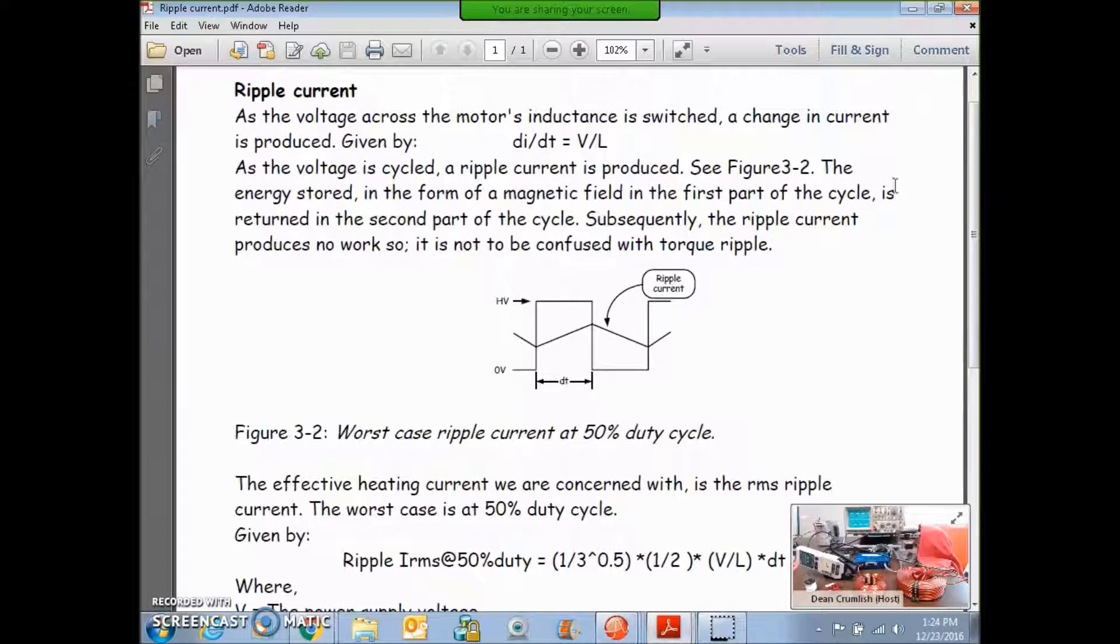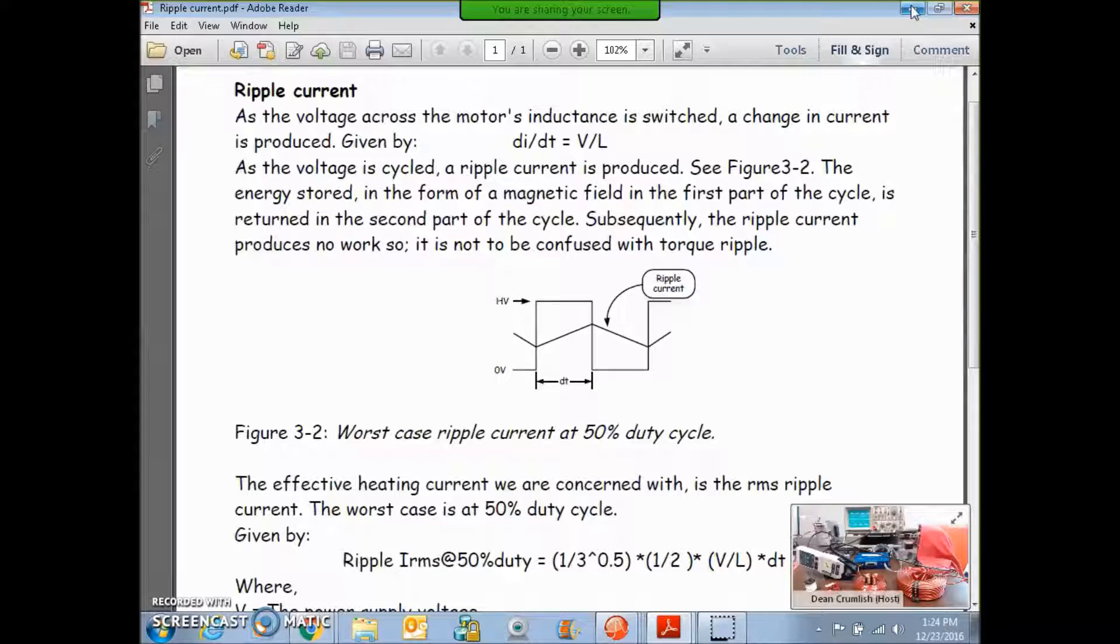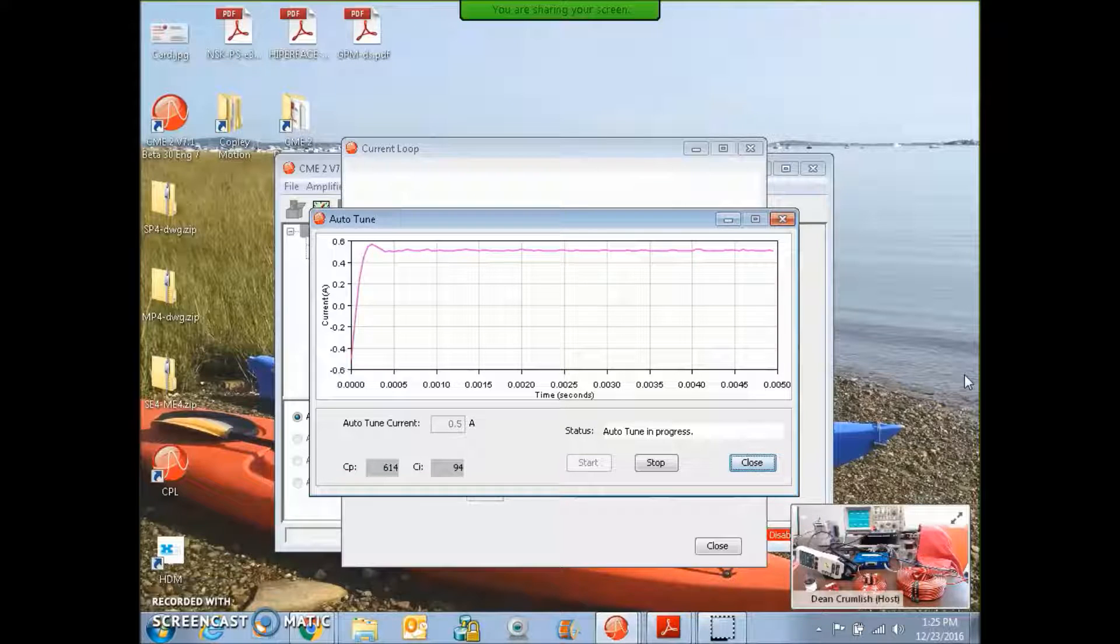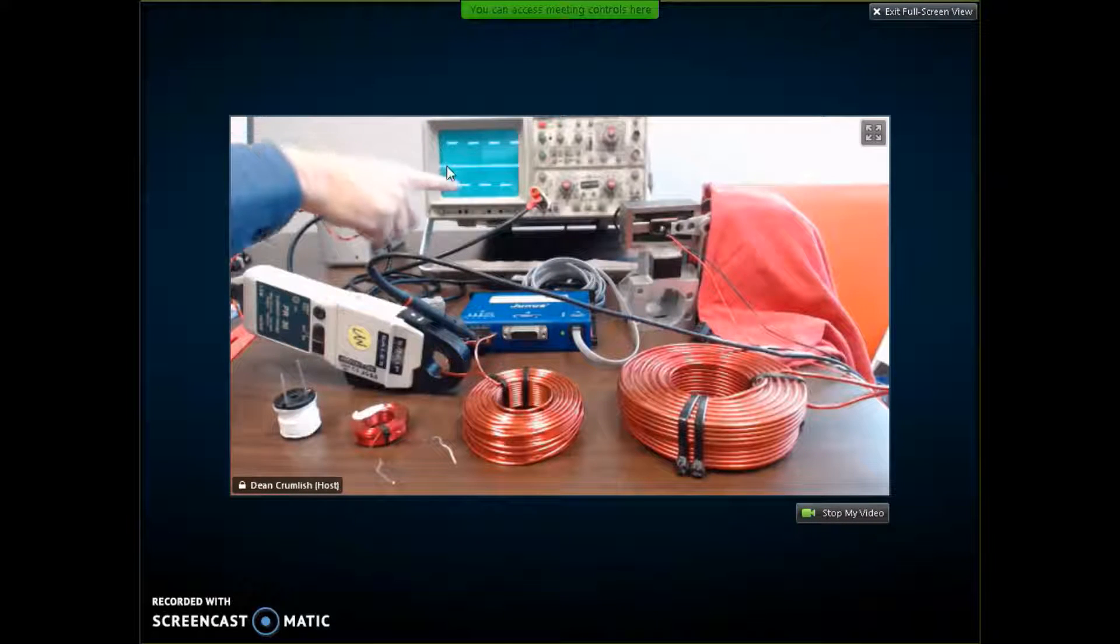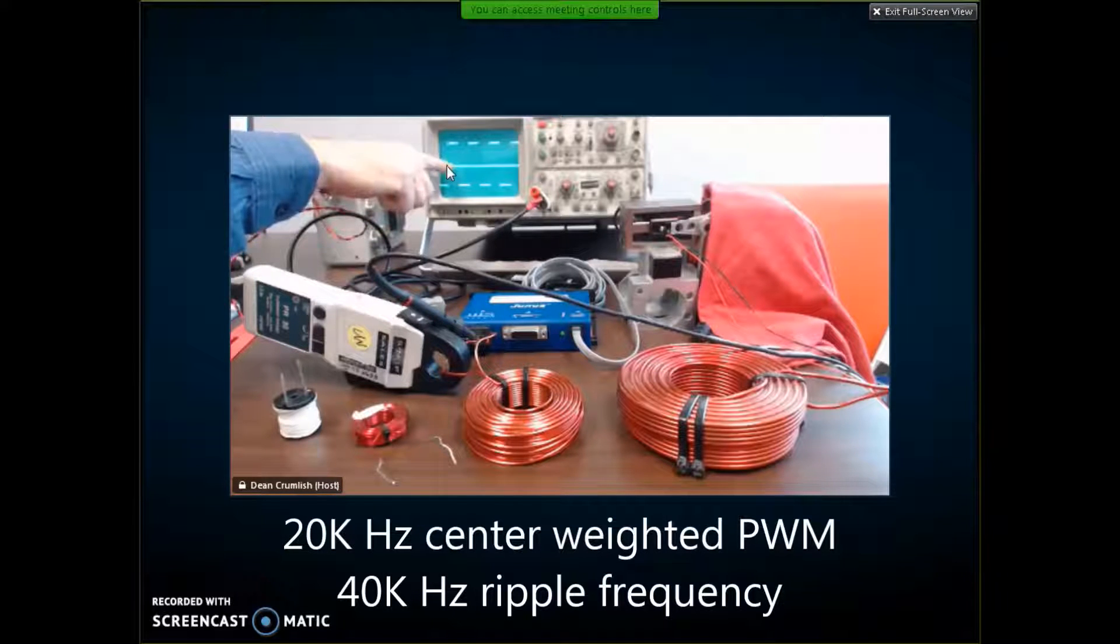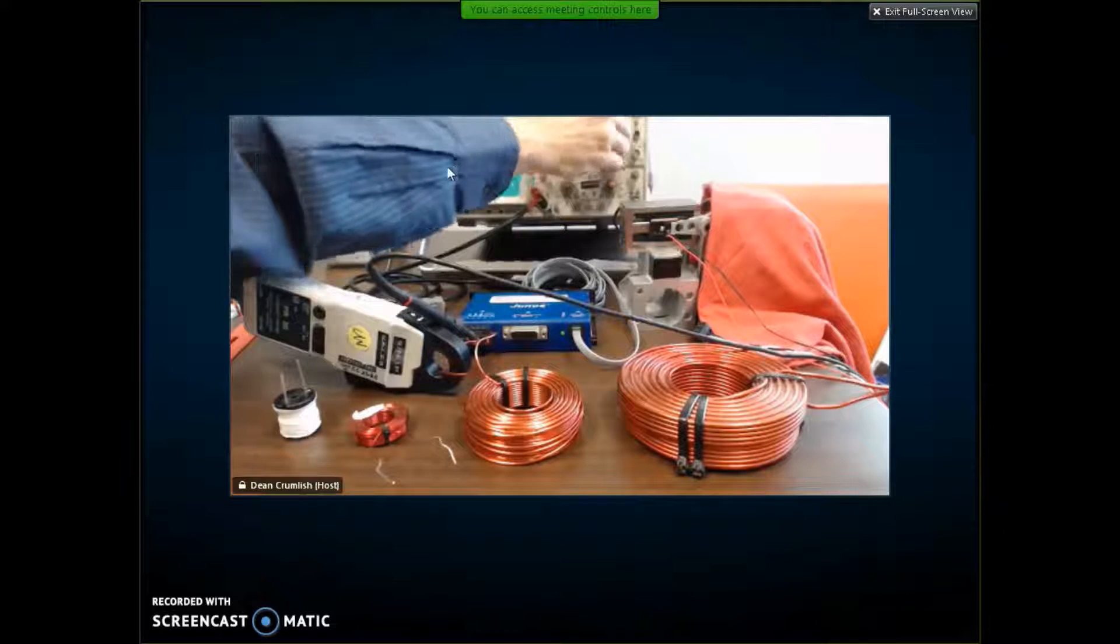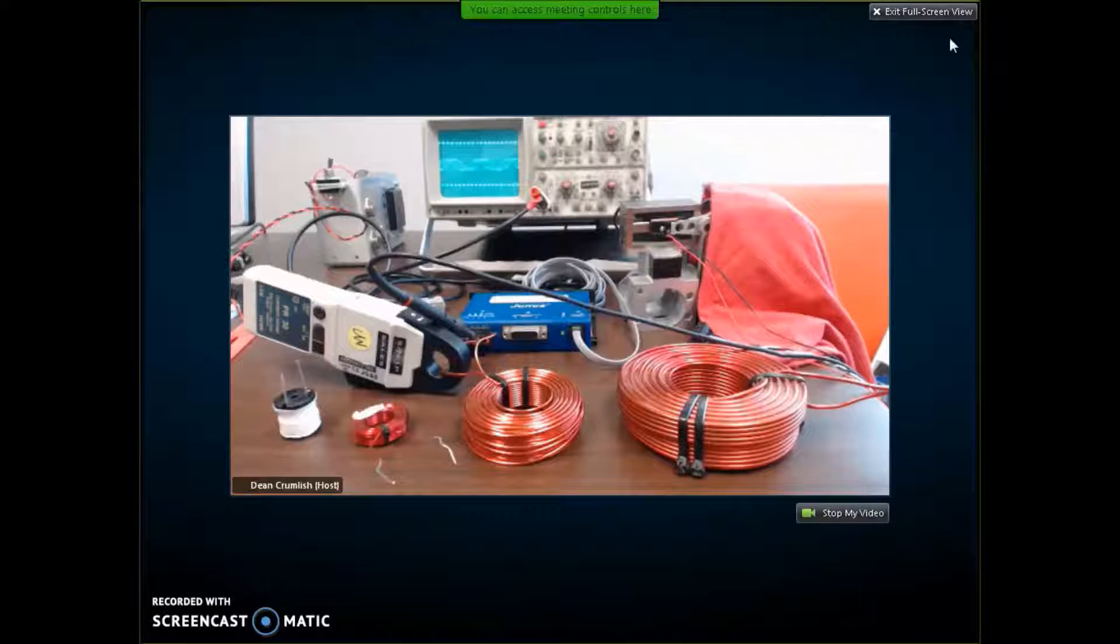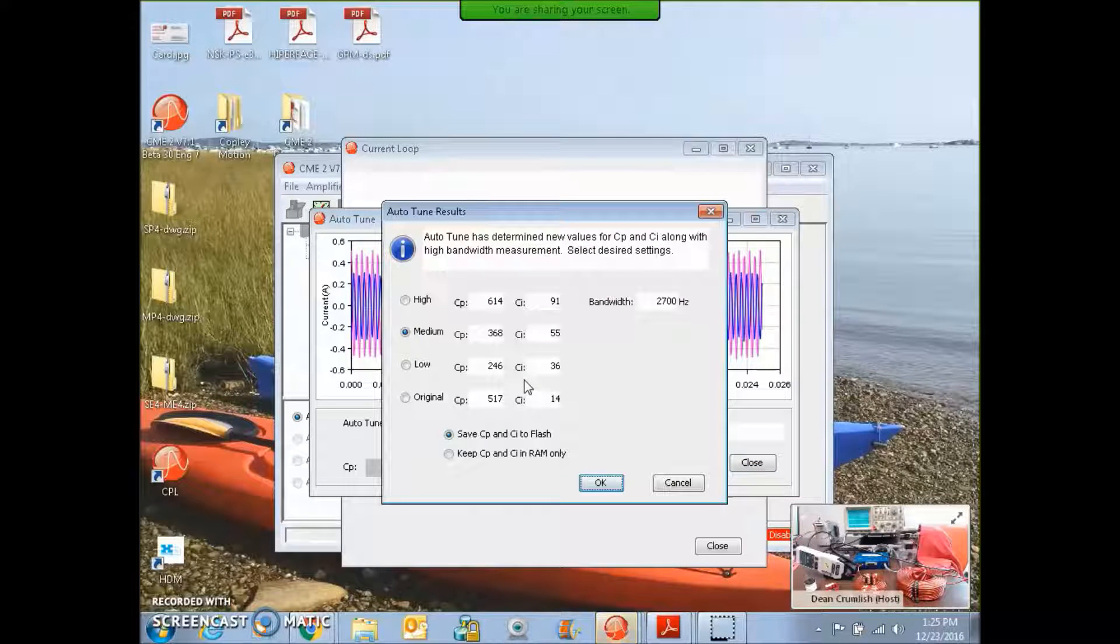The other effect of that PWM is the ripple current and we'll take a look at that in a minute. The current loop tuning is progressing. It takes a little time to do that so we'll just let it do its thing. But we can see on the scope there is a PWM effect at the output of the drive which is controlling the current. We don't see much current here, but you can see the sine wave that the auto tuning is generated.